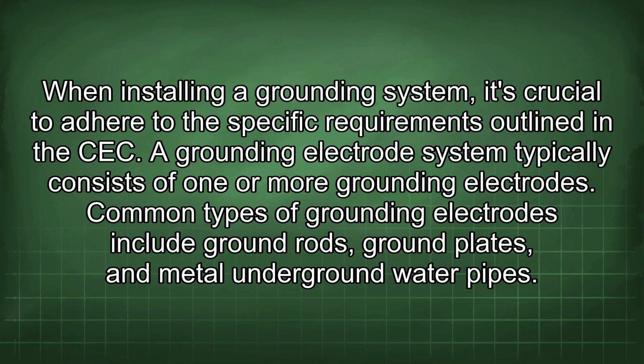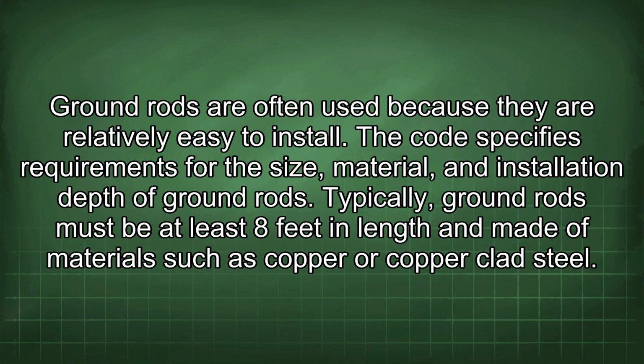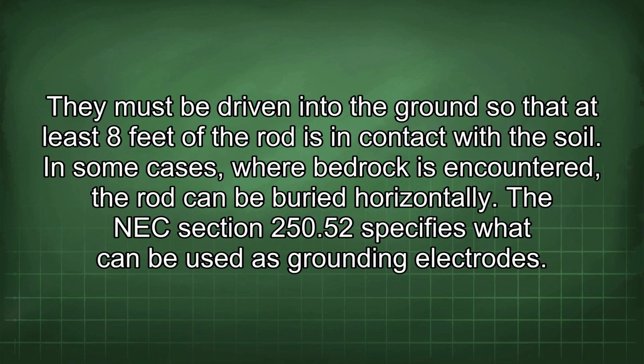A grounding electrode system typically consists of one or more grounding electrodes. Common types of grounding electrodes include ground rods, ground plates, and metal underground water pipes. Ground rods are often used because they are relatively easy to install. The code specifies requirements for the size, material, and installation depth of ground rods. Typically, ground rods must be at least 8 feet in length and made of materials such as copper or copper-clad steel. They must be driven into the ground so that at least 8 feet of the rod is in contact with the soil. In some cases, where bedrock is encountered, the rod can be buried horizontally.